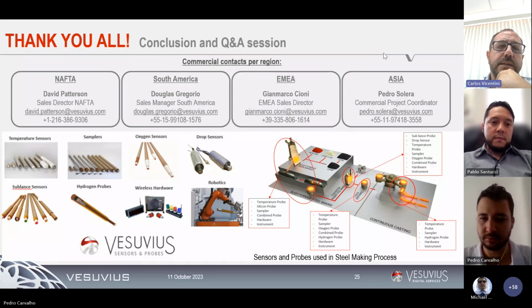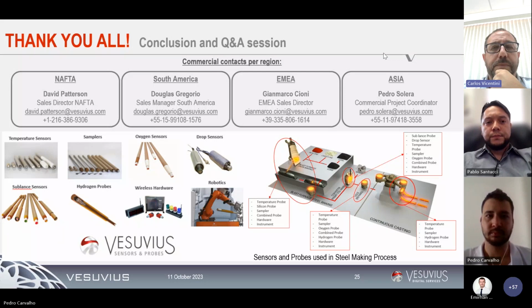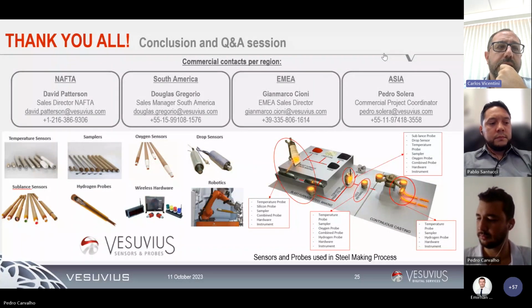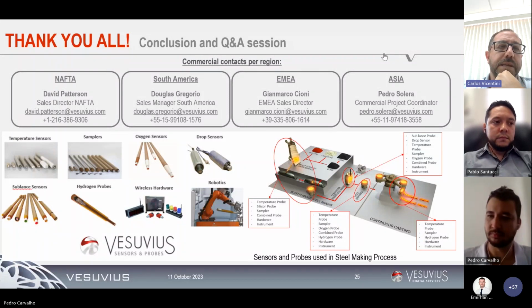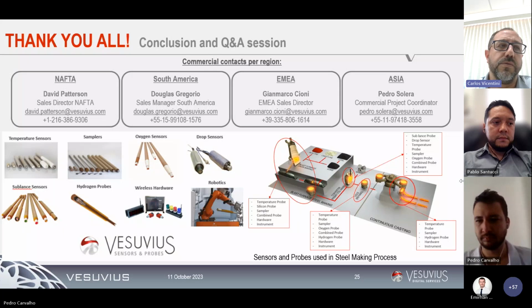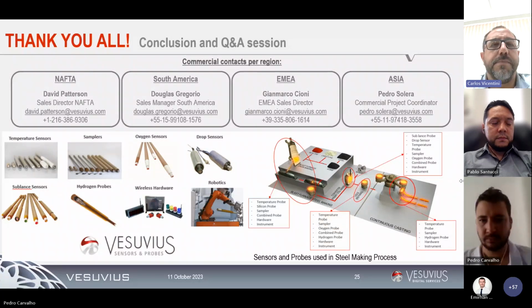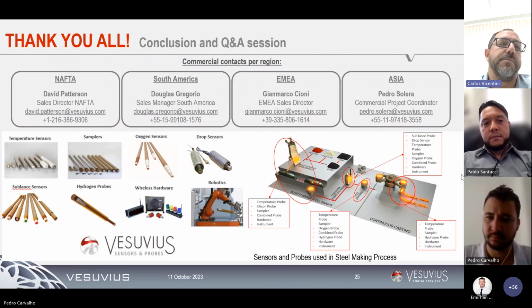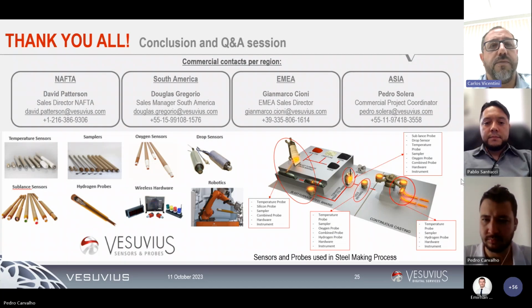But it's very important to highlight that the procedure to compare these results with the pin is very restricted. Of course, as you know, taking a sample by vacuum pins demands a lot of care to avoid contamination and hydrogen pickup. Usually when you run trials or tests with pins and check the repeatability, you don't get good repeatability, especially because it is affected by the procedure, which is very restricted. Of course, our system is more robust and avoids this kind of pickup during the measuring process.